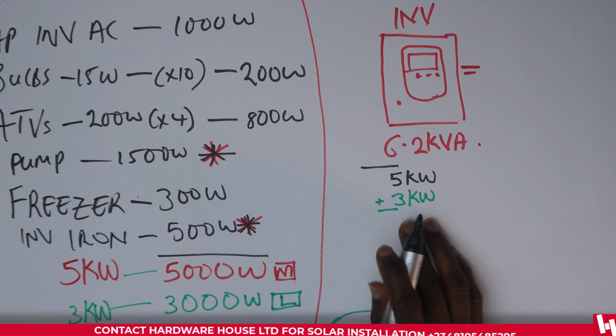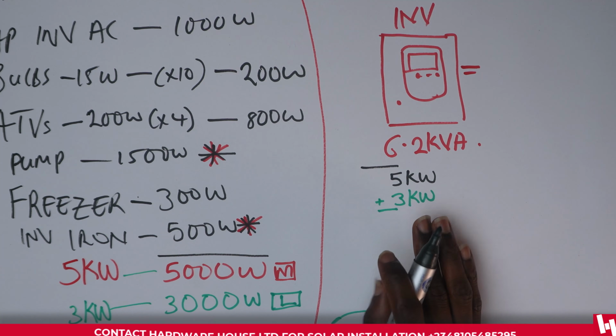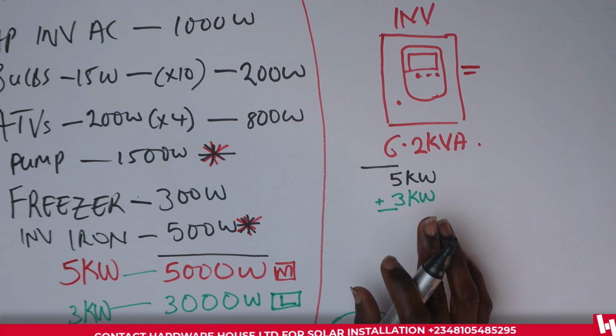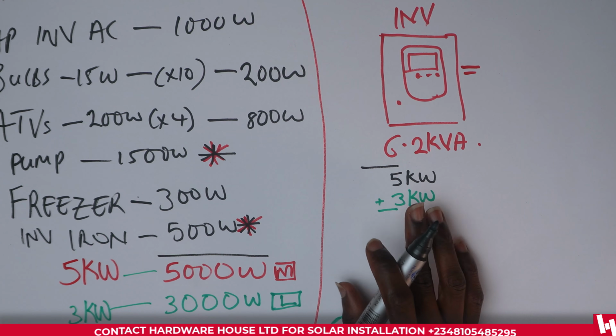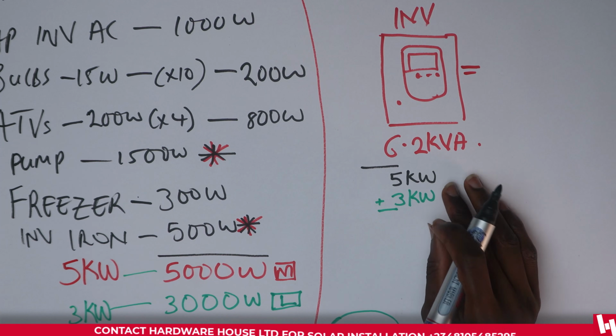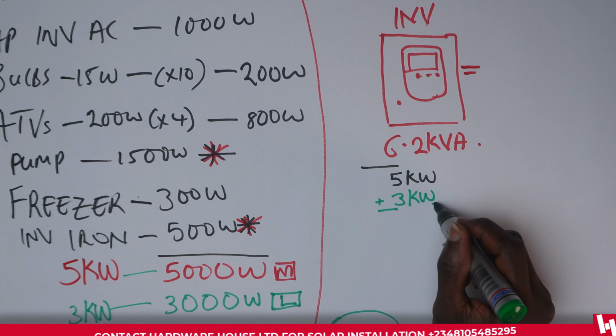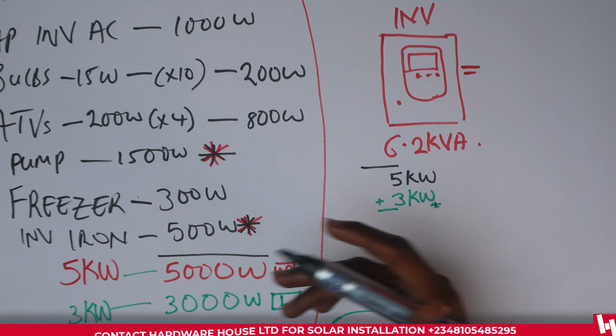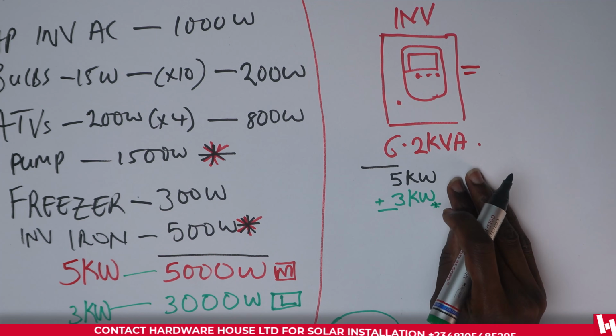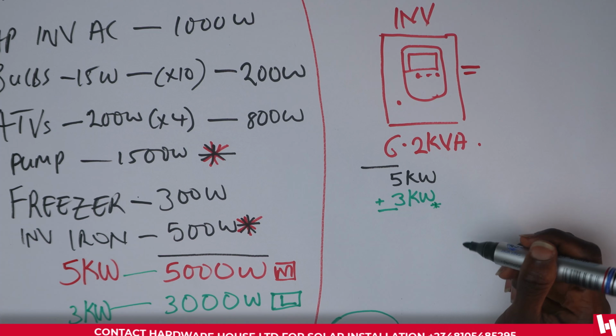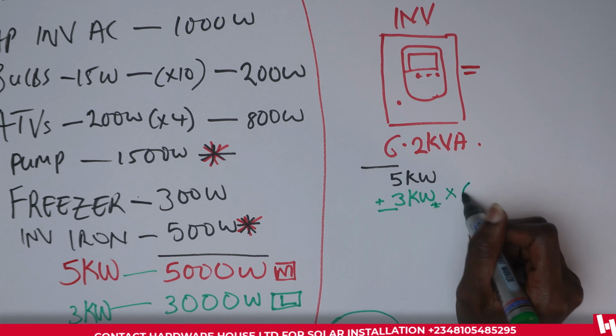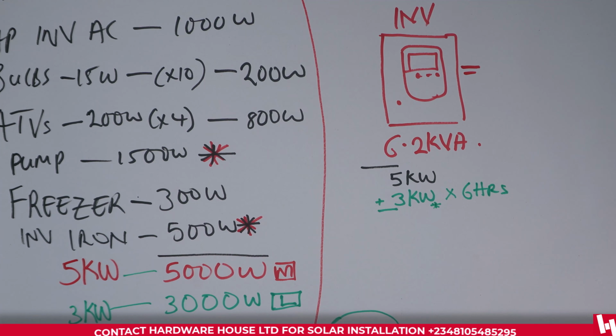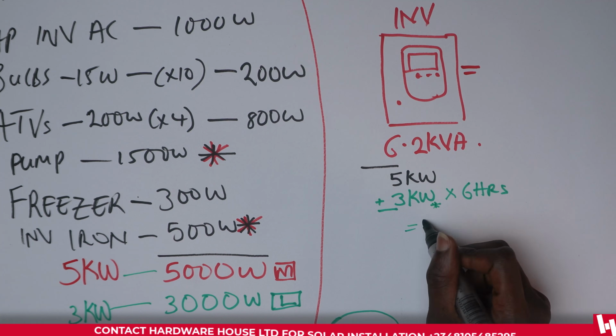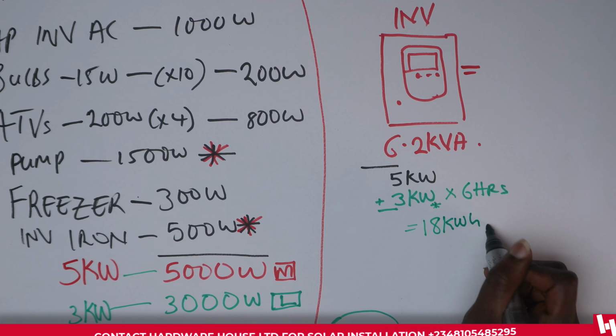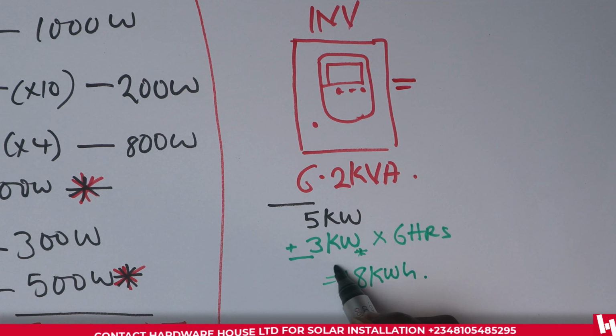We want to give 6 hours runtime on full loading, which means both ACs are on, the bulbs, the TVs, and the freezer are on all through the night. So we want to give our client 6 hours of this usage at night without the solar panel, with a lot of allowances on these loads and the 2 ACs running, a very budget-friendly design. So we would be giving him 6 hours. And for that 6 hours, if we consume 3 kilowatts every hour, that is 18 kilowatt hours. So here is the power that we need from the batteries.